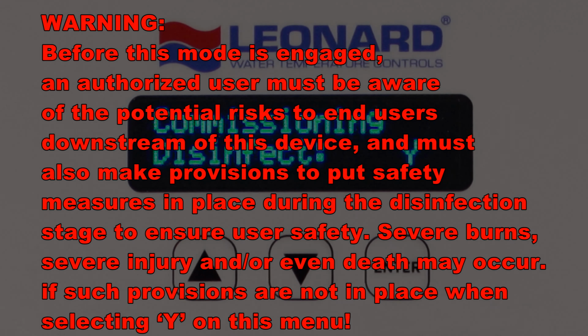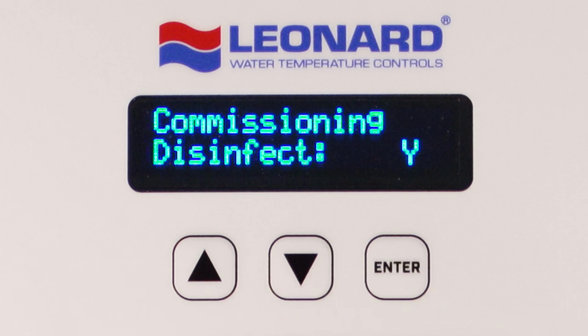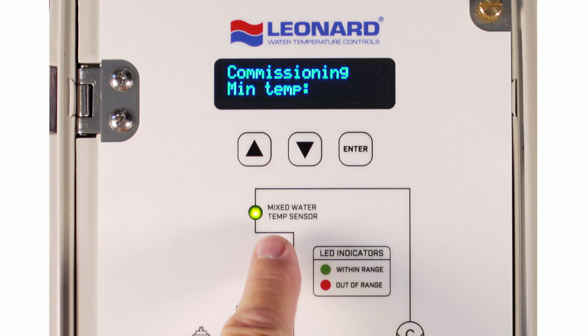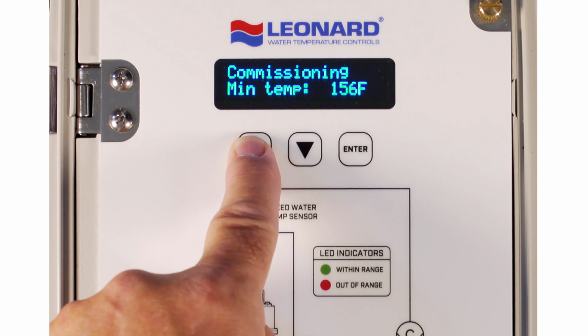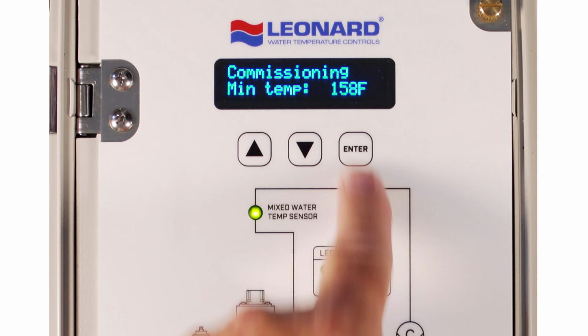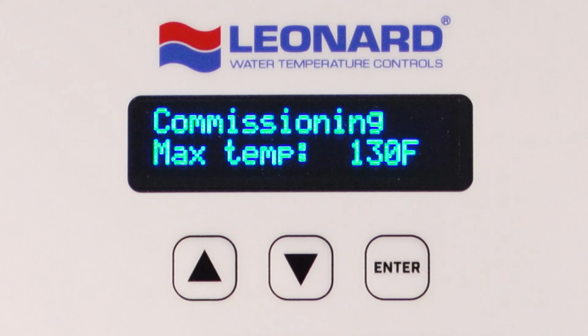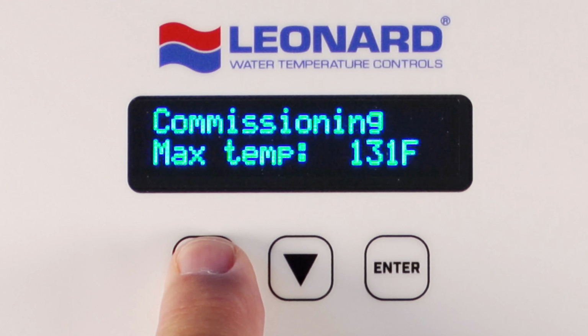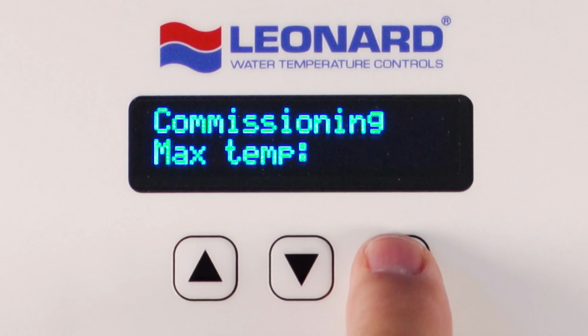Y on this menu. Before a disinfection cycle is initiated, the min and max settings must be changed to accommodate higher outlet temperatures. Min setting should be set to the minimum desired disinfection temperature. The max setting should be changed to the maximum desired disinfection temperature. After the first minute of disinfection, an error will be triggered if the outlet temperature is below the min or above the max settings, which will automatically end the cycle.